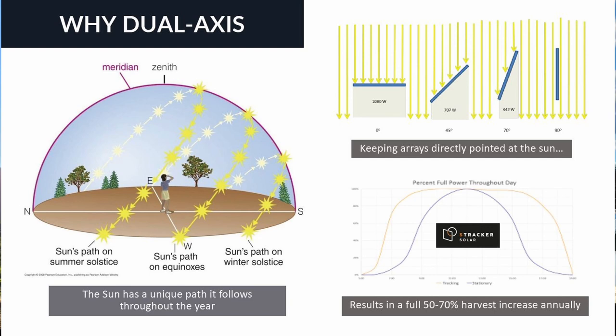To be fair, if you increase the carport tilt from 5 degrees to somewhere between 15 and 45 degrees, our energy harvest is only 50 percent greater than the carport. But oftentimes we'll see east-west-facing carports at 10 degrees, which is equivalent to that 5-degree south. Strackers also show about a 65 percent lower greenhouse gas footprint per kilowatt hour produced, because the power from the PV modules is increased and each module accounts for more than 90 percent of a typical PV system's embedded carbon.